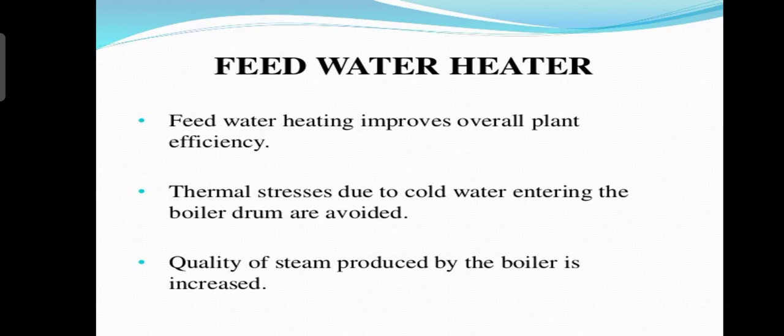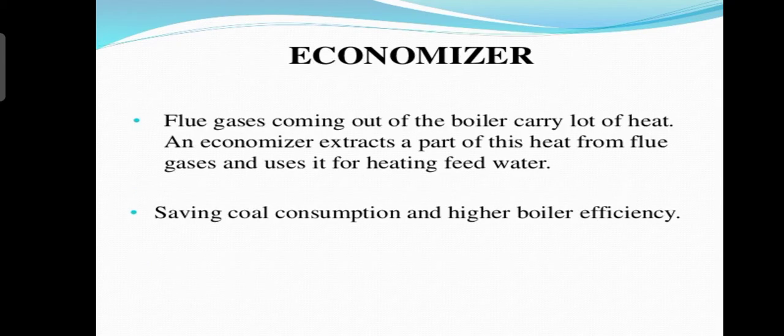Feed water heater. Feed water heating improves overall plant efficiency. Thermal stress due to cold water entering the boiler drum is avoided, and the quality of steam produced by the boiler is increased.